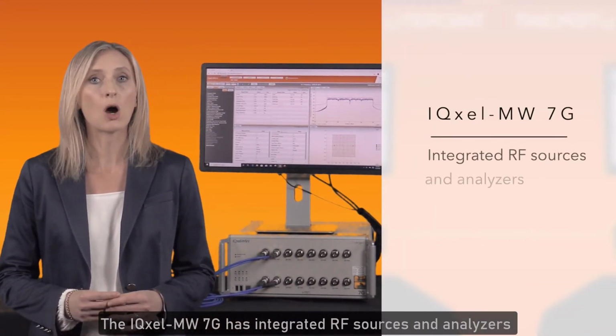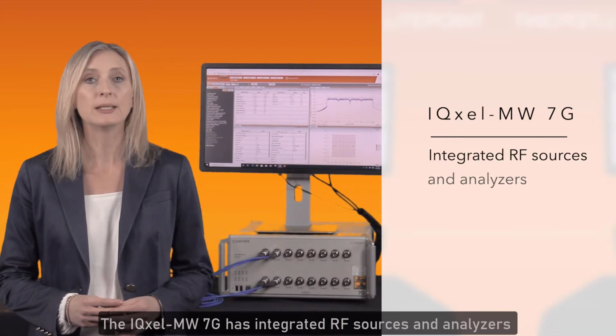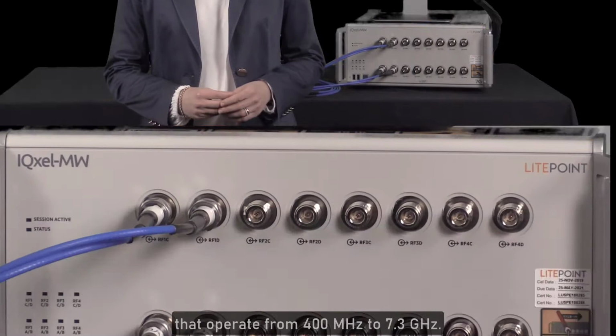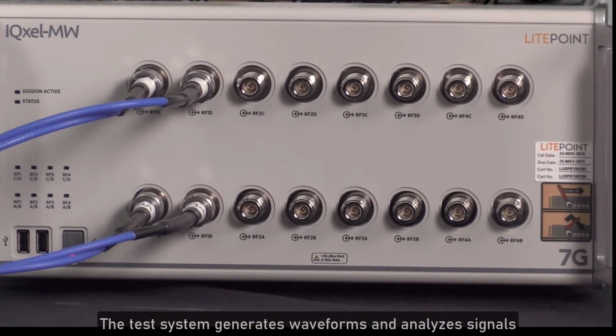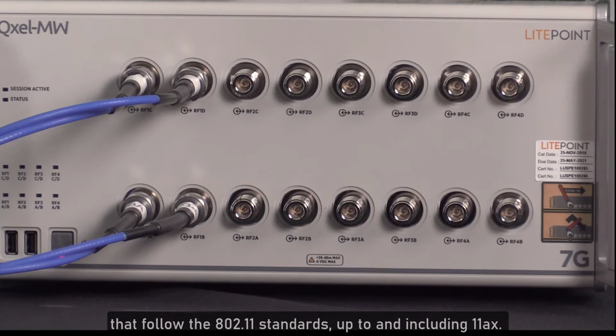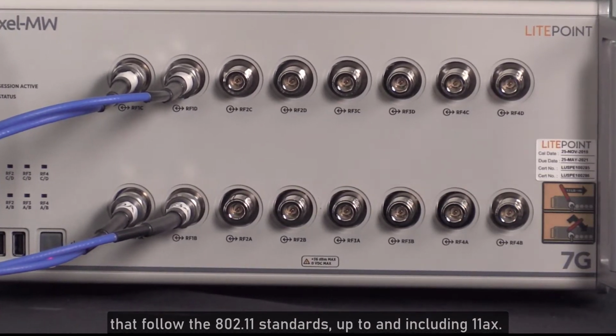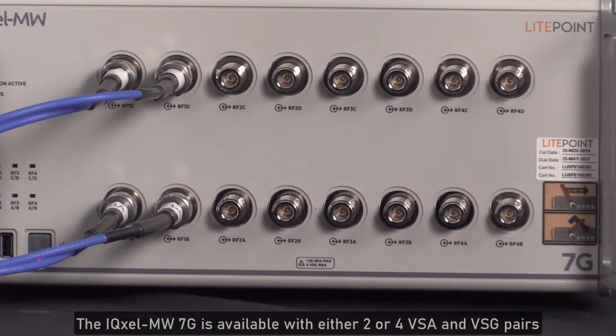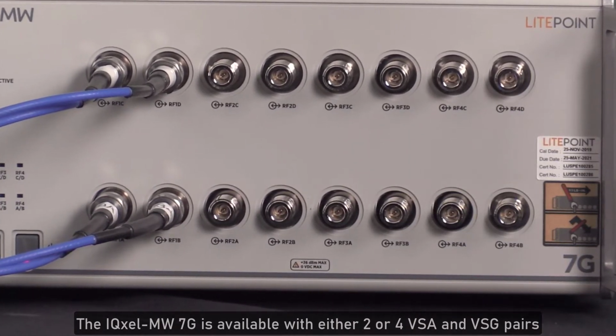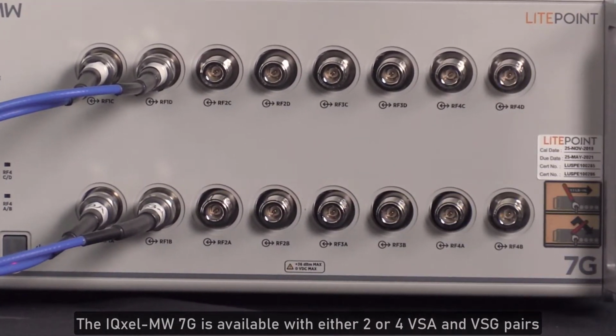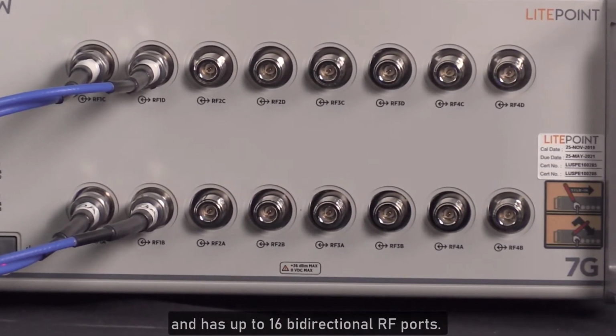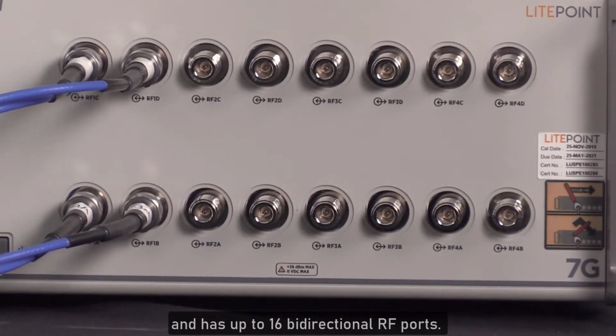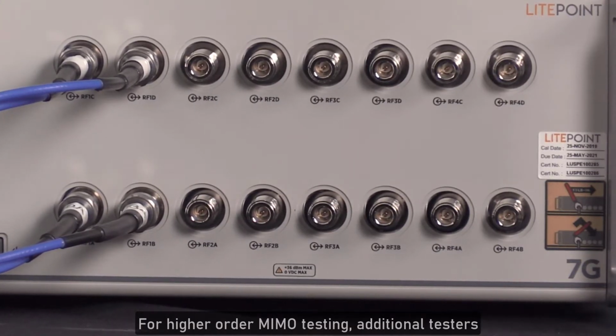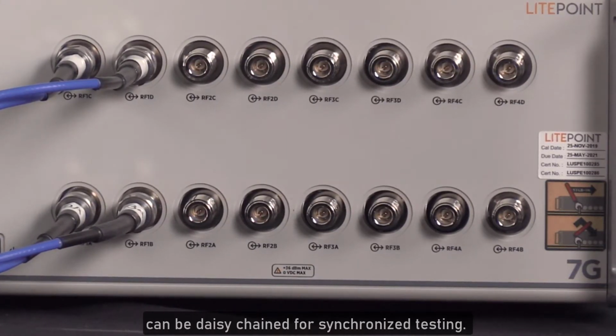The IQxel-MW 7G has integrated RF sources and analyzers that operate from 400 MHz to 7.3 GHz. The test system generates waveforms and analyzes signals that follow the 802.11 standards up to and including 11ax. The IQxel-MW 7G is available with either 2 or 4 VSA and VSG pairs and has up to 16 bidirectional RF ports. For higher order MIMO testing, additional testers can be daisy-chained for synchronized testing.